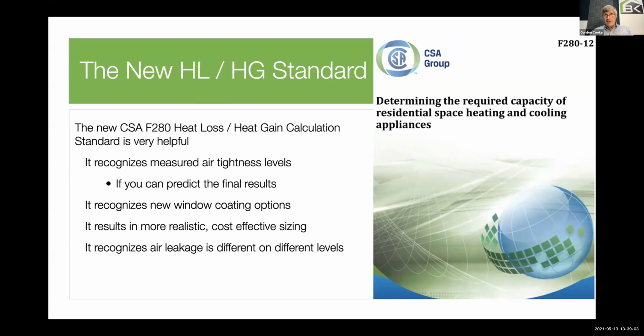And on the hottest days, it's actually not as humid as you might think because it's hot. And as you know, if you warm air up, it expands and its relative humidity goes down. So the design cooling day, that is the hottest day, actually almost always has a lower dew point than the design dehumidification day. Of interest, that design dehumidification day is not in the National Building Code. It is in ASHRAE, but only in the last 10 to 15 years. That is, we never used to think about this. And in fact, heat loss, heat gains do not take into account the humidity outside. They actually don't. They just apply that 30%. They do not look at the humidity outside as being part of the cooling load. So hopefully that answers it.